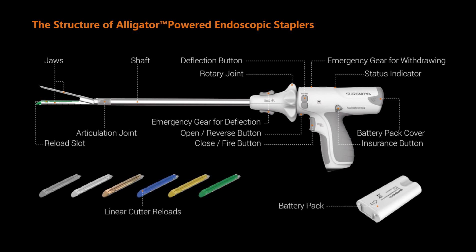The stapler cannot be disassembled except the battery pack cover. Its main functional parts include close fire button, open reverse button, deflection button, rotary joint, insurance button, and emergency gears.